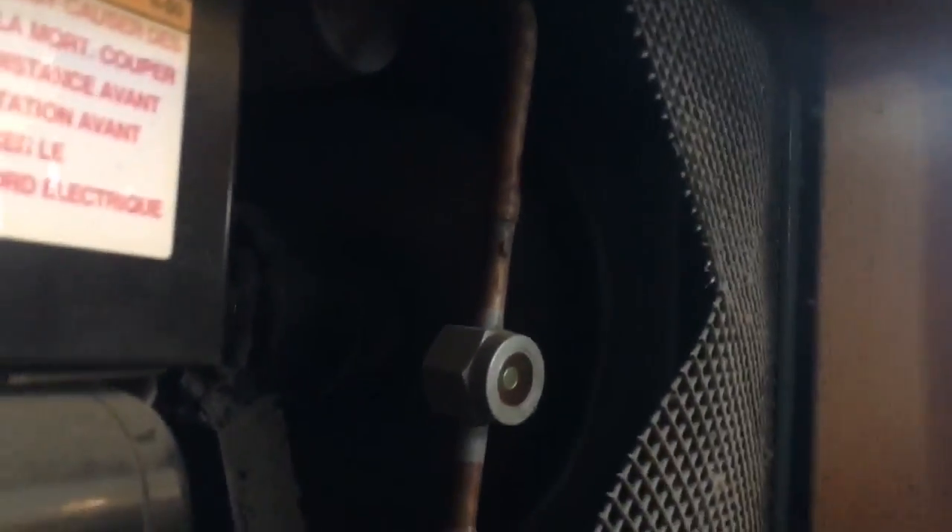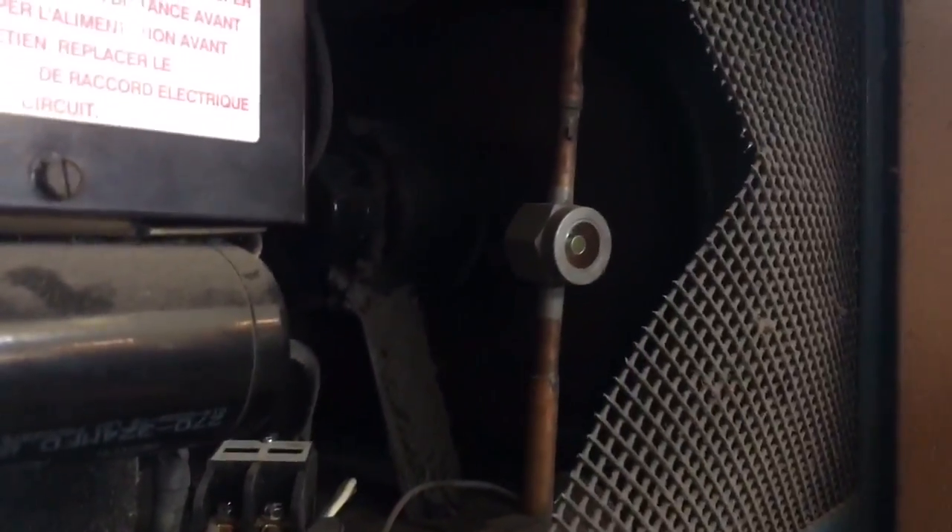For the new guys, we might check the liquid line right off the start, and it's so hot it's burning my fingers, so I got a plugged condenser. Absolutely, 1,000% plugged condenser.